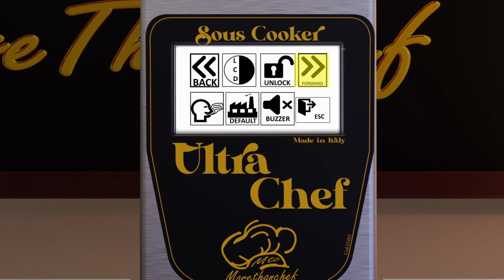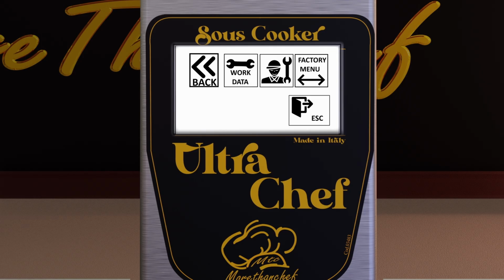Continuing on the settings screen and pressing the forward button takes you to the next page. Button number 7 is dedicated to technical support service. It contains useful data for analyzing the use of the device, such as the total number of cycles, the maximum, average, and minimum temperatures reached, the total working time at set points, the average timer set by the user, and the overall operating time, including heating. With button number 8, you can access the information needed to contact support. Finally, button number 9 allows you to enter special menus reserved for technical support centers, which are password protected.